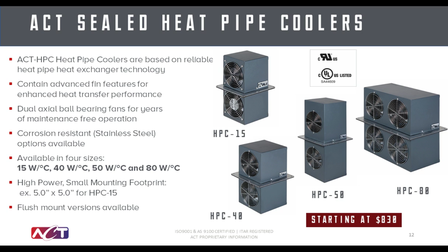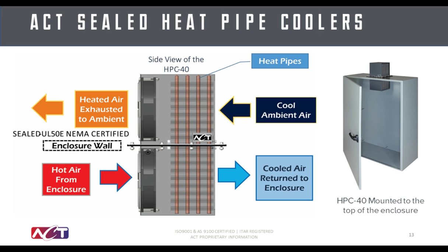Again, expanding upon the operation of this device, we'll walk through again, starting in the enclosure, going through the process of heat transfer to the external portion of that enclosure. Hot air from the enclosure is blown across a fin structure again to the first portion of heat pipes, where heat pipes start operating and removing heat from that airstream. Cooled air is then returned to the enclosure as the heat is transferred to the external portion of that HPC model. Using a fan, cool ambient air is blown across that heat pipe fin structure and exhausted to the ambient air.